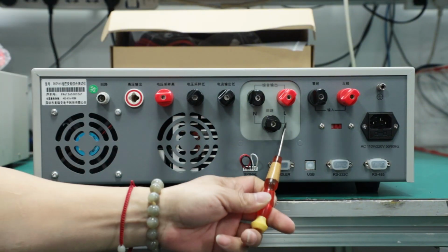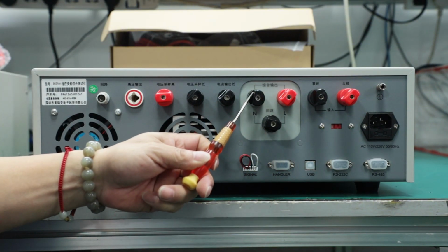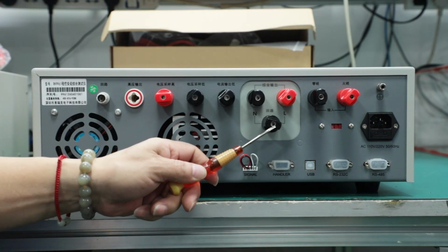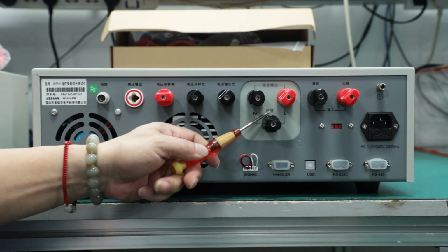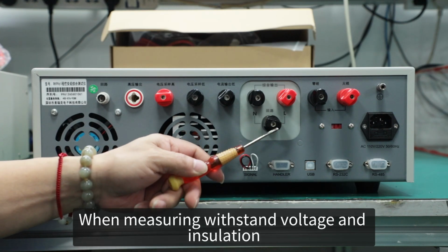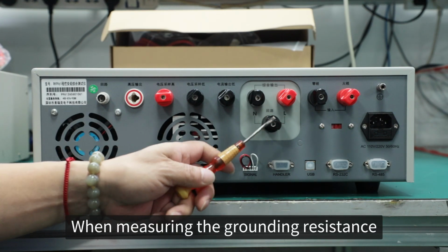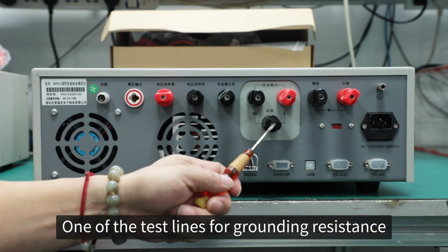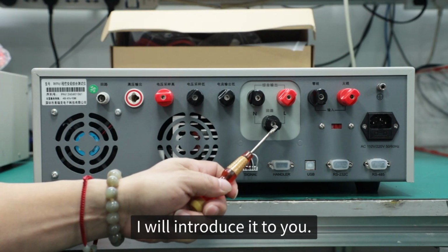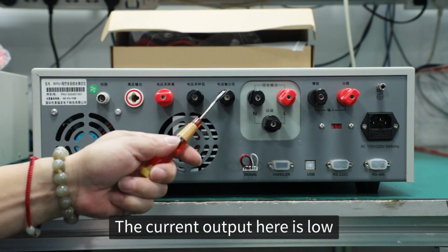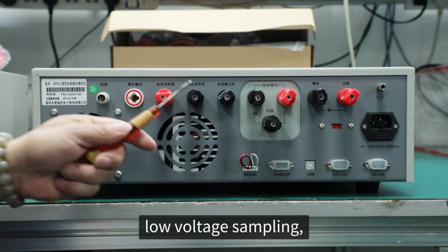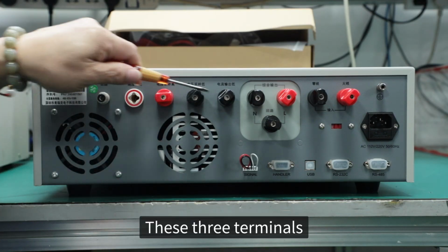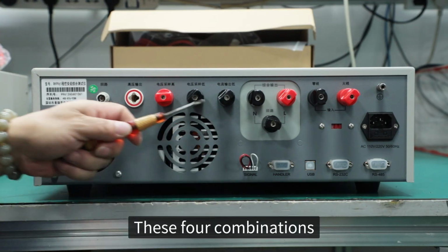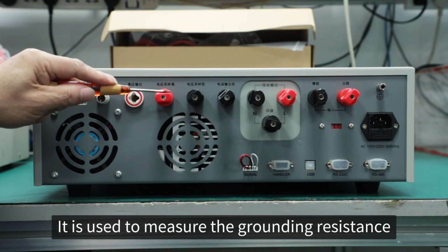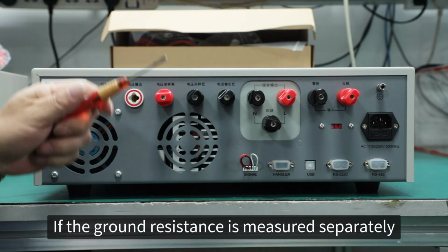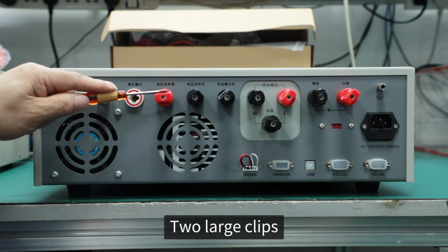Here are the signs. LN stands for live and neutral line. The black pillar below is marked loop. It is the loop when measuring withstand voltage and insulation. It is equivalent to a high voltage circuit when measuring the grounding resistance. Then here is one of the test lines for grounding resistance, I will introduce it to you. The current output here is low. Low voltage sampling. High voltage sampling. These three terminals, plus this loop, these four combinations are used to measure the grounding resistance. If the ground resistance is measured separately, use two large clips.